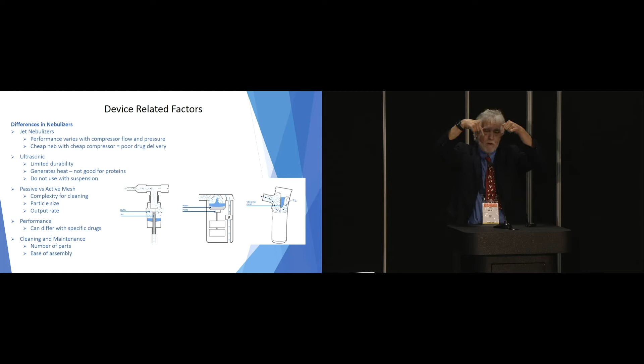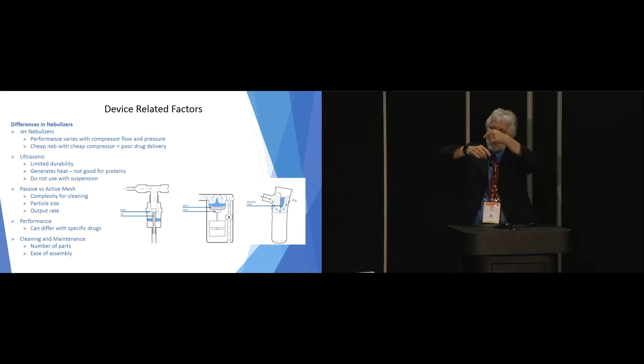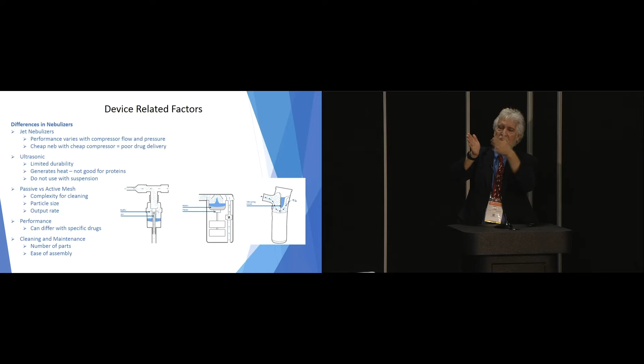It works with suspensions as long as the suspension particles can fit through a 4-micron particle mesh, and generally budesonide is about 2 microns, so it's not a problem. Performance can differ with specific drugs with any nebulizer. So if you have an active or a passive mesh, an active mesh is one where the mesh is vibrated by a piezo that surrounds the mesh component. A passive is where you have an ultrasonic horn that's kind of pushing drug through and causing it to vibrate.